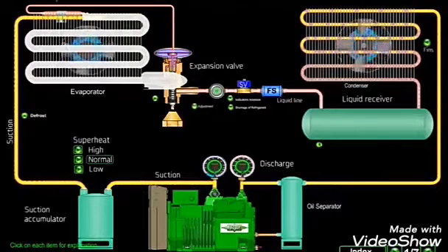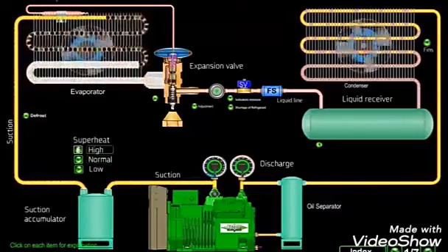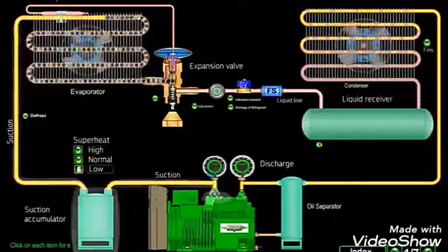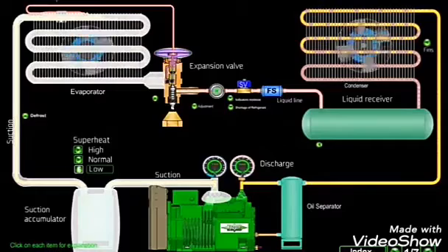The refrigerant evaporates in the evaporator, absorbing the heat necessary for its transformation from liquid to vapor. The refrigerant should leave the evaporator as a superheated vapor. This degree of superheat is to protect the compressor, as it can only compress a vapor.